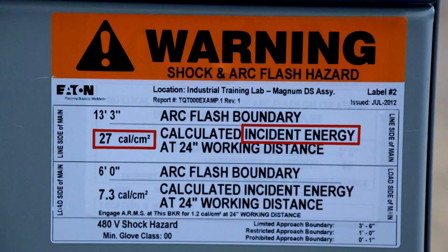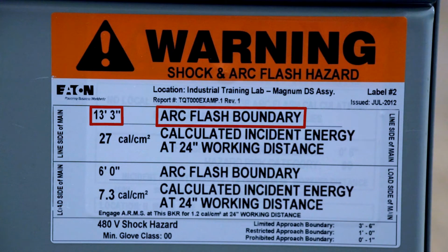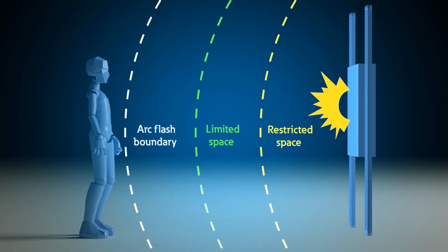Incident energy is the energy that would arrive on bare skin or on the surface of any garment you are wearing during an arc flash event, expressed in calories per centimeter squared. The arc flash boundary is the distance from the energized equipment to the point at which the incident energy drops below 1.2 calories per centimeter squared. PPE requirements indicate the type of clothing required to protect a worker against the incident energy at the working distance as indicated on the label.